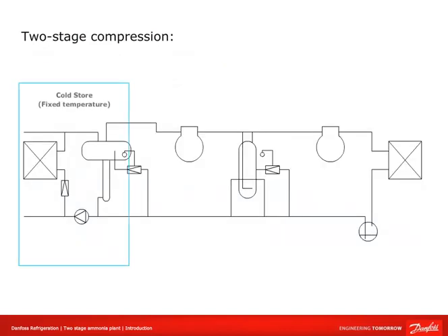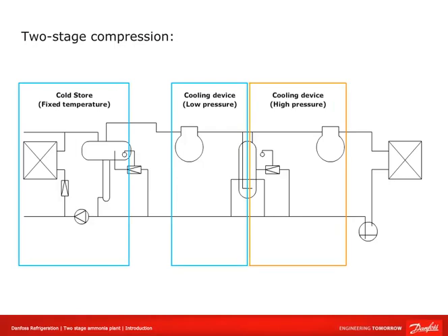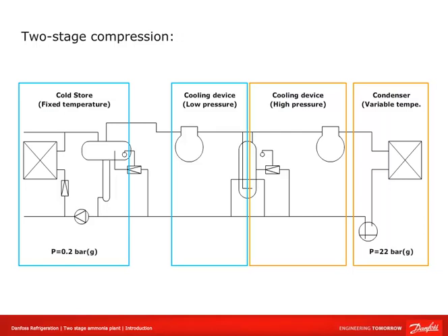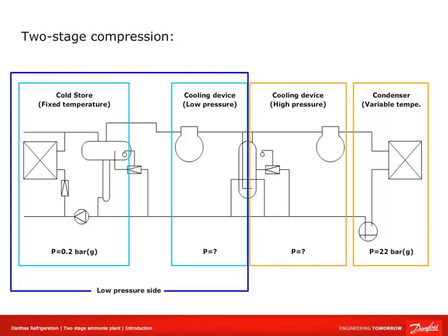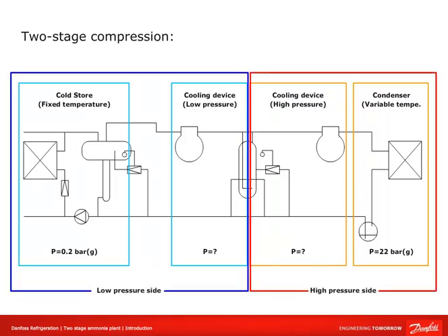In this diagram we have a cold store with a fixed temperature, a cooling device for low pressure, a cooling device for high pressure, and a condenser. The cold store room temperature is fixed; there must be a pressure of 0.2 bar to maintain that temperature, and the condenser pressure is 22 bar. We don't yet know the temperature of the low-pressure cooling device, the discharge temperature, or the suction pressure of the high-pressure cooling device. With the low-pressure and high-pressure sides identified, we can now calculate the two-stage intermediate pressure.